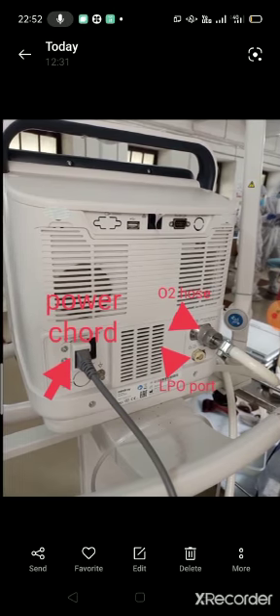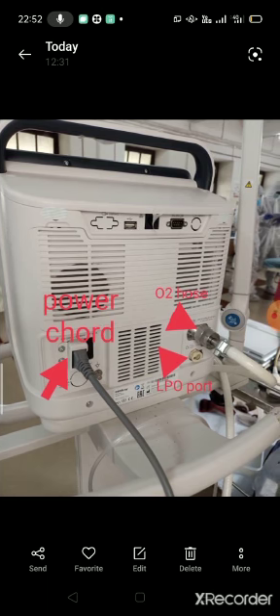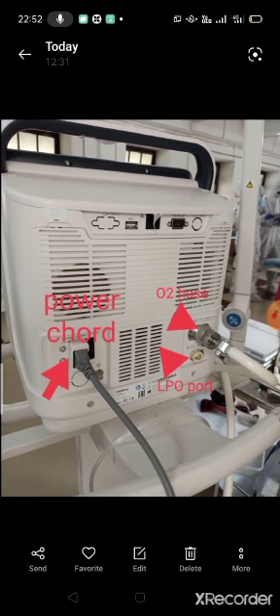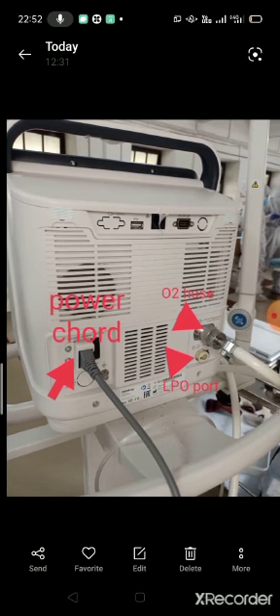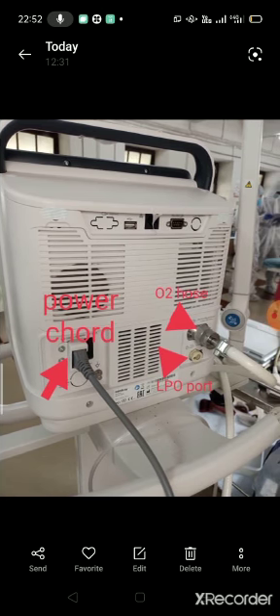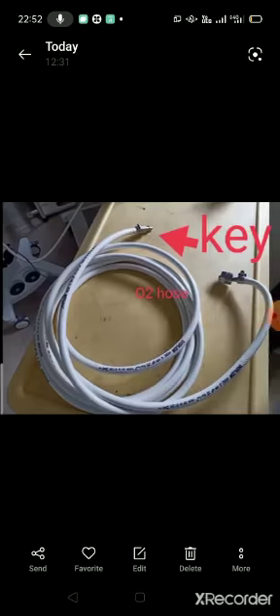In the case when you are using the ventilator for portable purposes, you don't need to connect the O2 hose at the back. You will have the O2 supply from the O2 flow meter, which is connected to the B-type cylinder or any other type of cylinder. So normally it is B-type. Now you will be wondering where the air supply will come from. Air will be generated through a turbine inside, and the room air will be taken in through this filter at the back, and it will generate a high pressure air which is needed for mixing O2 and air. And this is the back side.